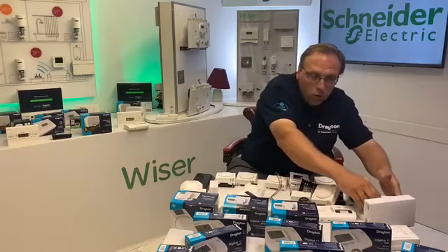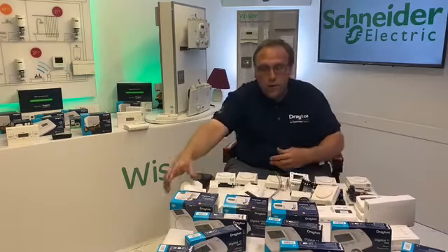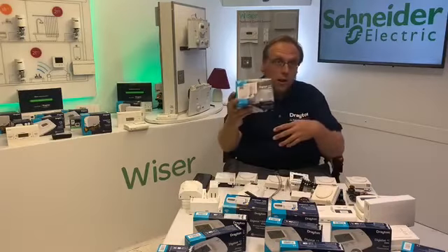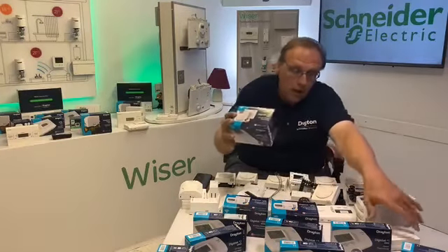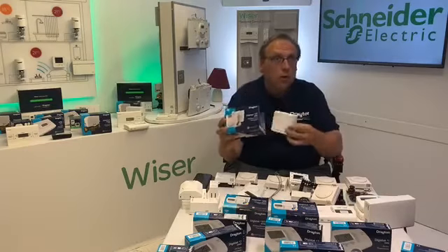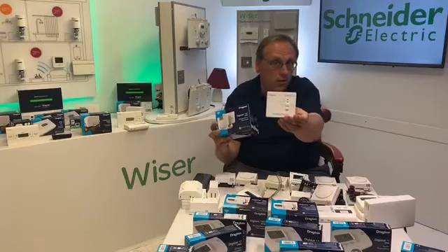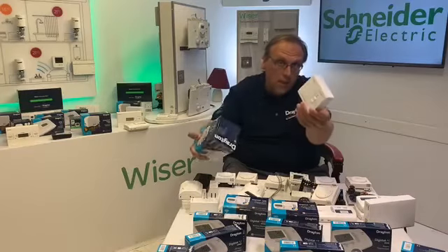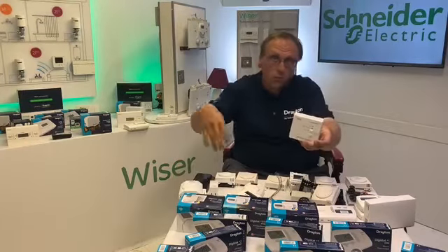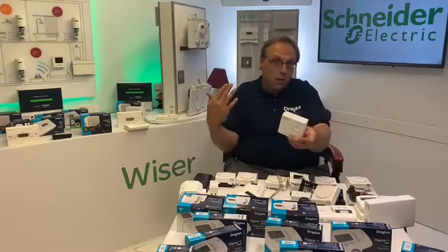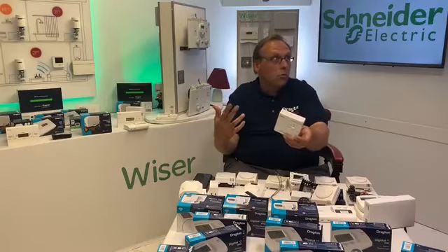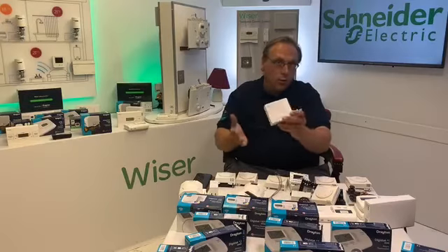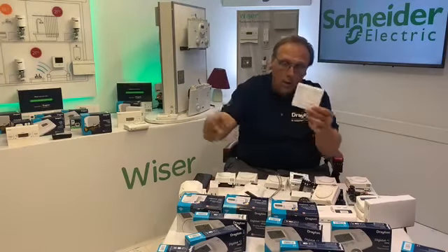Lastly, I'll move on to the RF versions of these. So exactly what we saw before, Digistat Plus, you get a Digistat Plus RF, and it's a wireless control that comes with an SCR, so that's your single channel receiver, is what SCR stands for. So this again is volt free, so it's a 4-wire control. You need a permanent live and neutral to run it, and then you've got access to your switch contacts, normally open and normally closed through that.